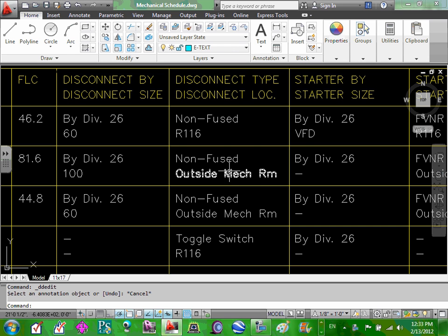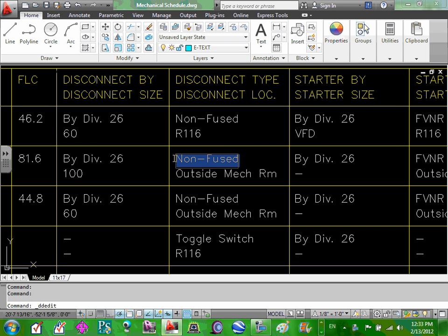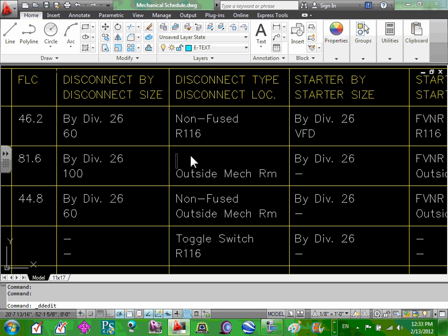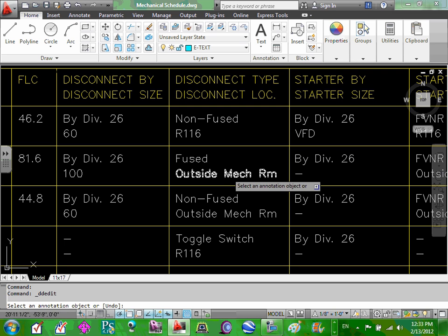All right. Now let's look at the type. The type, now Dustin is saying non-fuse, but Dustin, what did they say down here? They say a fuse. So what do you do? Very easy, you come over here and you get rid of the non-fuse, you're going to say fused. That's it. Okay, now disconnect type fused, disconnect location outside mechanical room. Because why? Because it says fuse disconnect adjacent to the equipment. The equipment is outside the mechanical room. It's going to be outside the mechanical room. Any questions about this? That's straightforward.